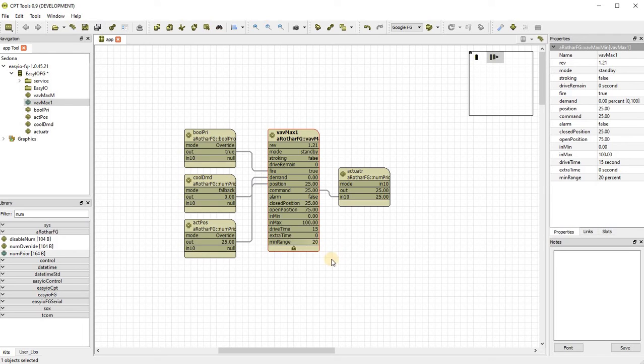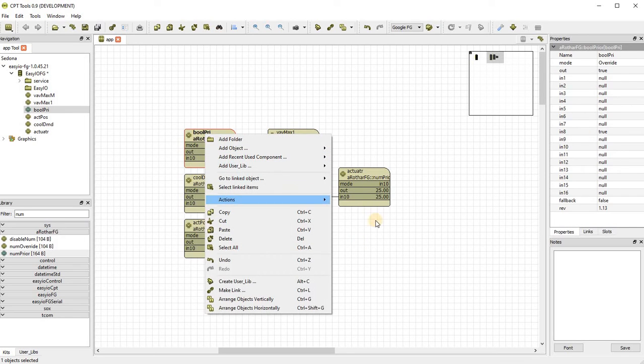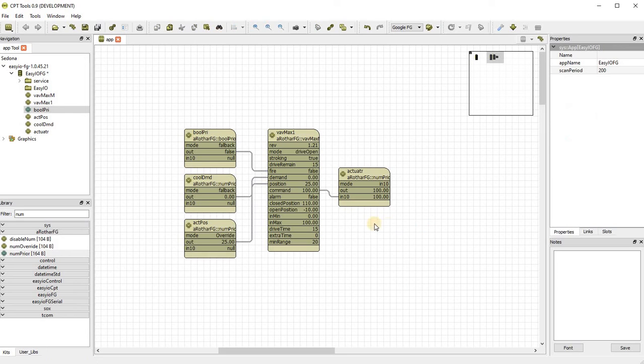What we also wanted to do was to be able to tell on maintenance whether the actuator was faulty or not, because now we can see the feedback. We can see if it's driving an appropriate distance. So we've put a minimum range on by default of 20%. If the range it strokes is less than 20%, the block will go into alarm and the input will result in the output with no rescaling. Let's have a crack at that so we can see what's going on.